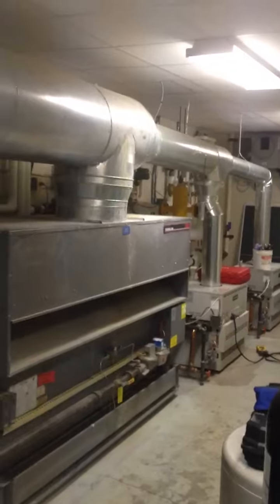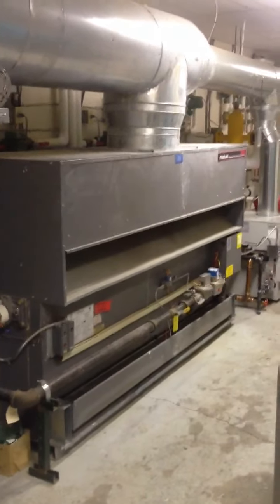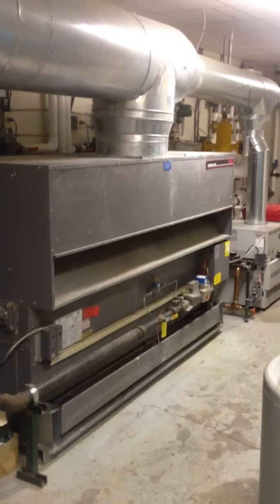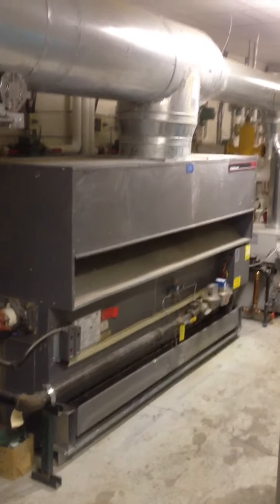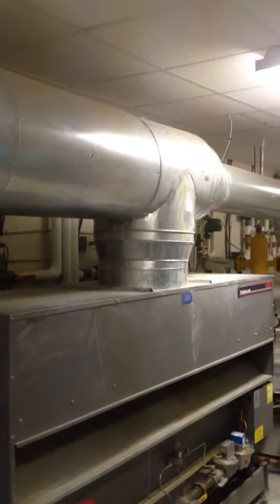It's a 1.8 million BTU Teledyne Laars boiler. So I'm seeing with the foil tape test that I need to add barometrics. Can I block this off and put the barometrics in the front of this diverter chamber, as there is no room to add barometrics to this boiler with what we have existing?